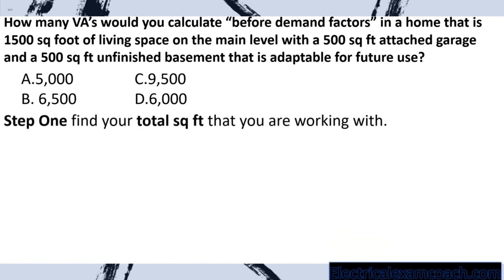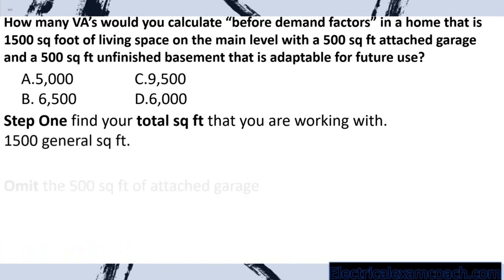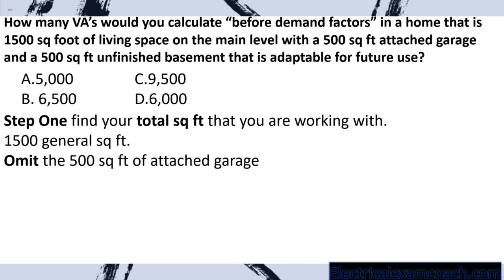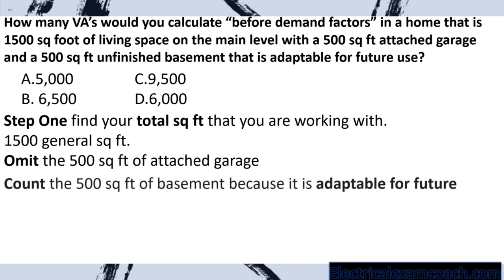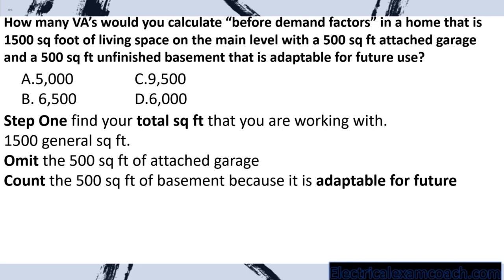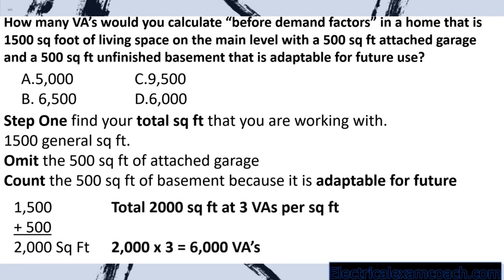Step one is to find our total square feet. We have our 1,500 general — we will count it. We omit the 500 square foot of attached garage. We count the 500 square foot of basement because it is adaptable for future use. In your testing it'll say either or, and in the real world it's almost always adaptable for future use. That gives us 2,000 square feet. We take 2,000 square feet multiplied by 3 VAs per square foot, and we select D.